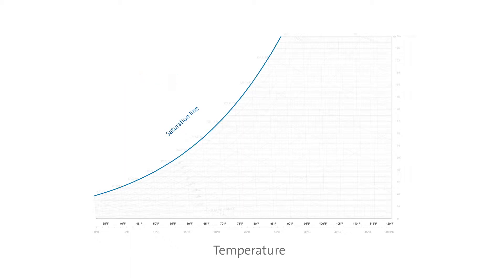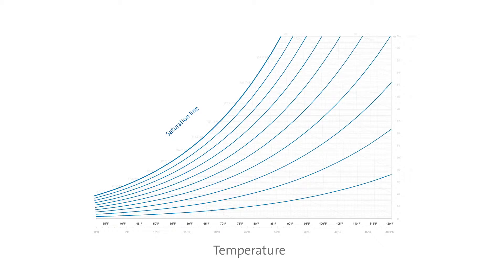In technical systems such as an air conditioning system, it is very important to know how close the humidity contained in air is from the saturation line — in other words, from what point onwards condensation will occur. The amount of water which air can absorb is therefore scaled from 0 to 100% and is known as relative humidity. Relative humidity is a percentile proportion describing the degree to which air is saturated and how close the air condition is to the saturation line.